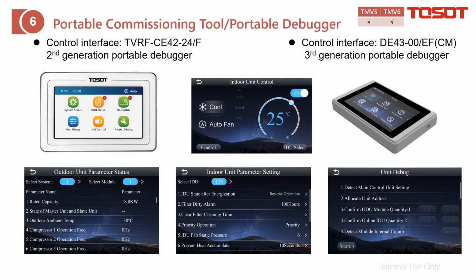This slide displays the control detail of the portable debugger. On the left side is the second generation CE42. On the right side is the third generation DE43. After you select your specified indoor unit, you can change the setting. Also, you can check the outdoor unit and indoor unit information and also the operating parameters. And besides, you can also do the system commissioning.